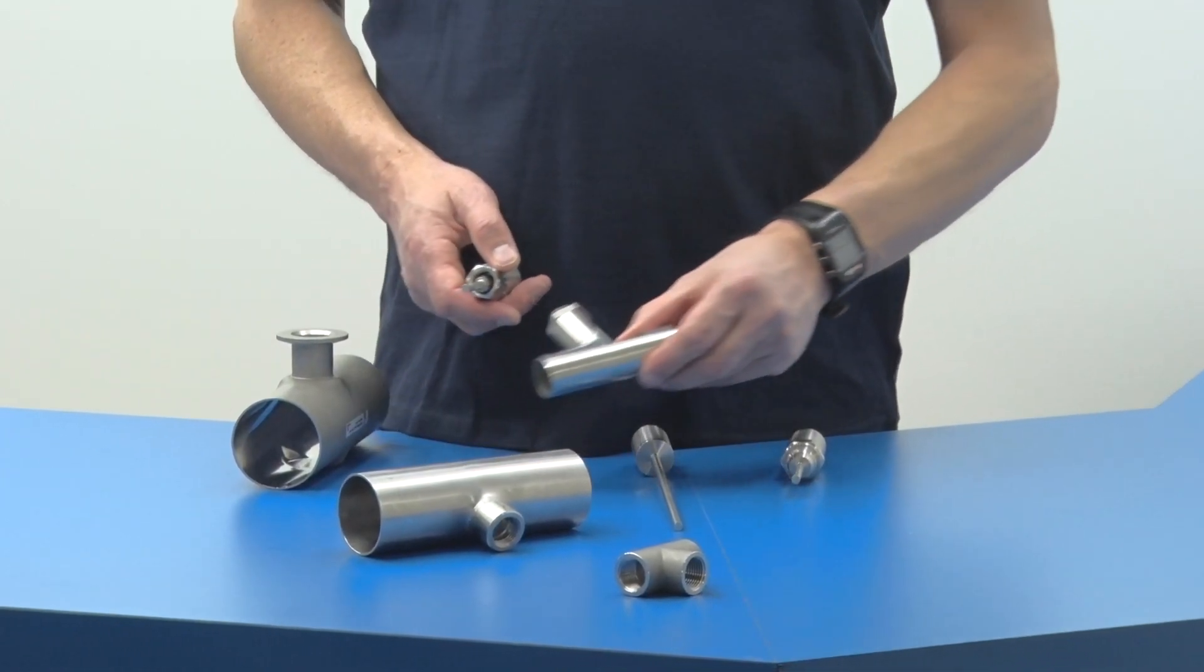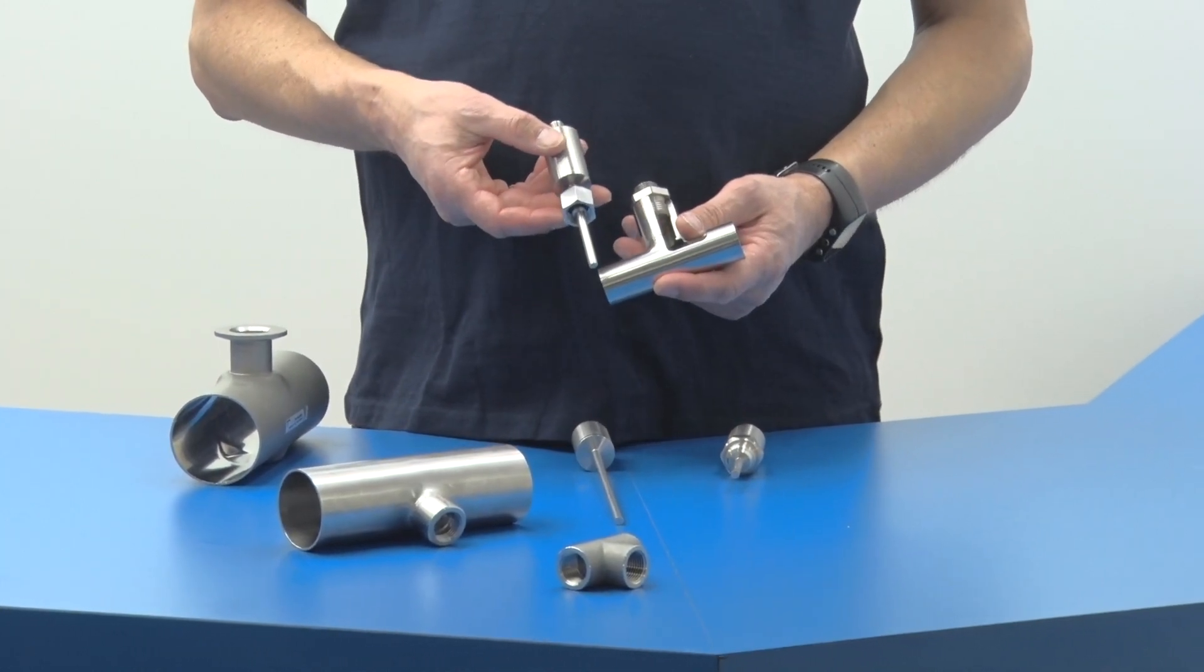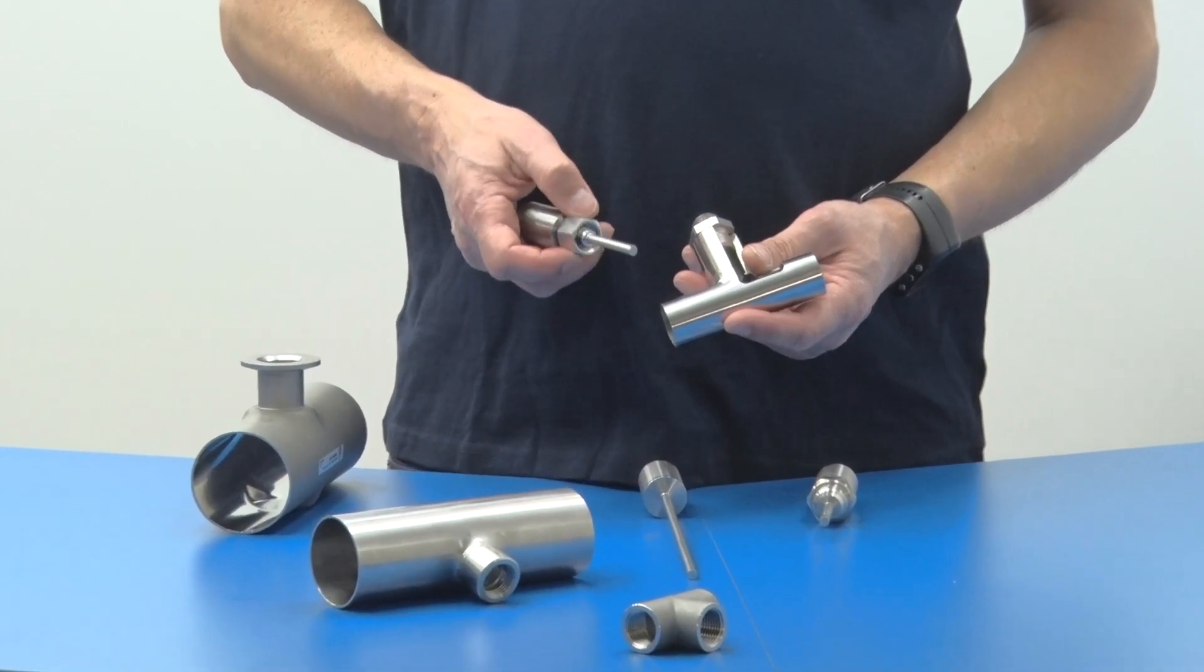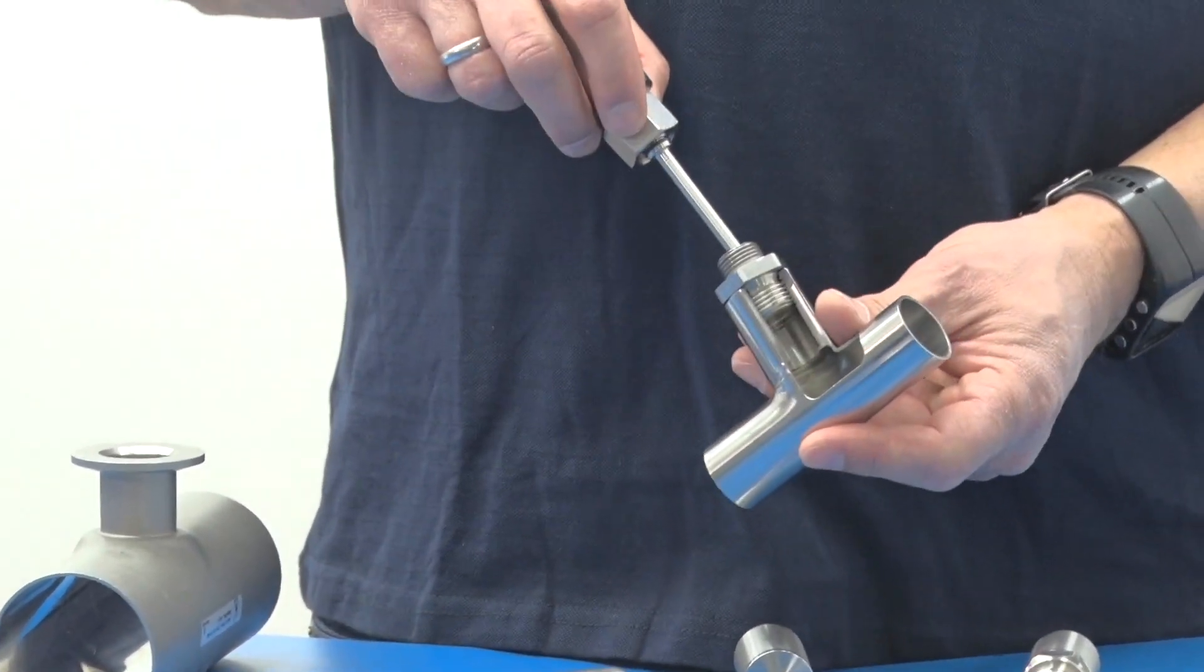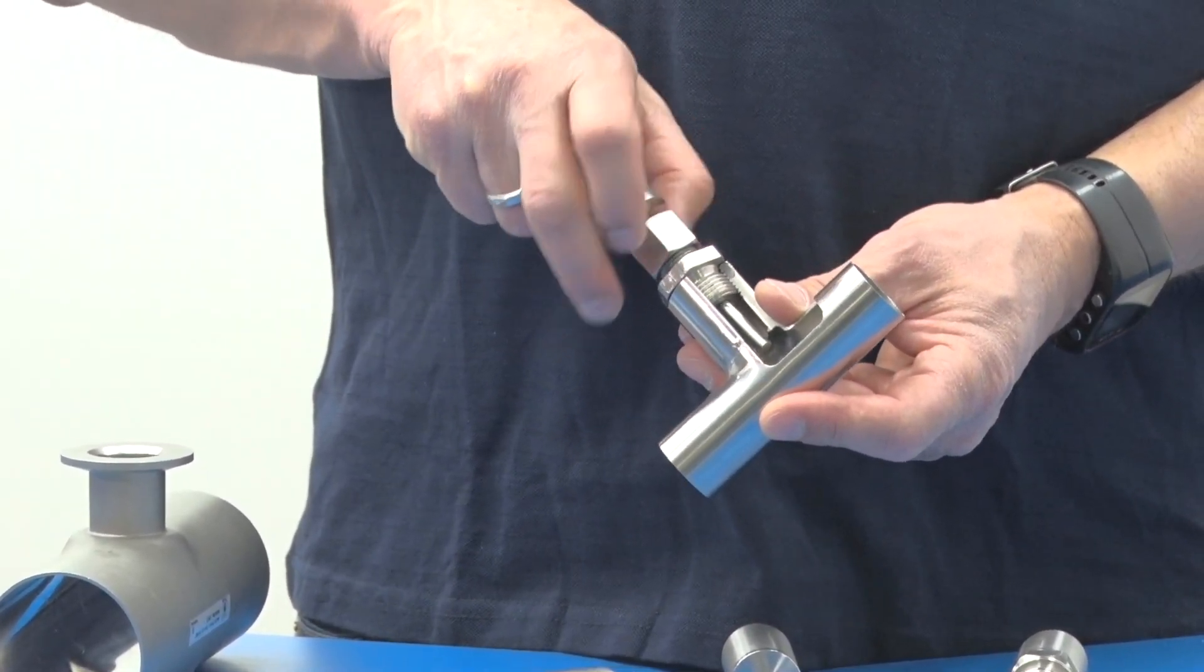If each pipe in the system has the same cross-section and high pressure is present, I recommend the sensor with sealing cone. The connection endures pressure up to 100 bar. Sensor mount is either using the screw adapter or the welded adapter on the pipe.